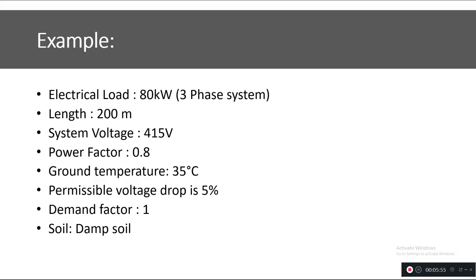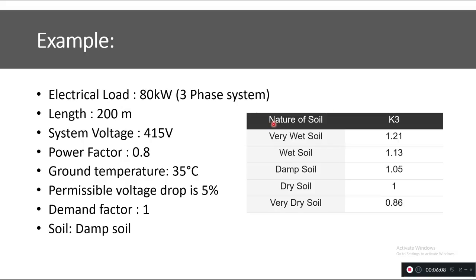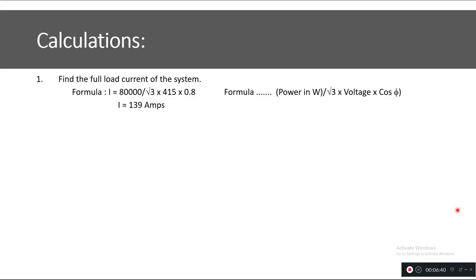If you don't have the thermal resistivity of the soil, you can refer to the chart shown on screen and select the factor according to your soil type. Now, calculating the full load current: using 80 kW, power factor 0.8, and 415 V in the three-phase formula P = √3·V·I·cosφ, the full load current is 139 A. You need to select a cable capable of carrying 139 A.